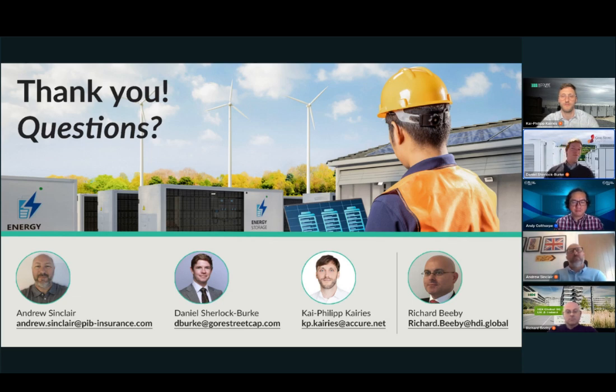I'm not aware of people doing that at the moment. You tend to go over at maintenance visits and do those imaging checks. But honestly, that's unlikely to catch the thermal runaway in time if it was going to happen. It's a useful tool for analysis of the performance of battery racks, and you should use it, but it's not a replacement for this software. It's not going to be as dynamic, and it's not going to warn you as early on, unless you're very lucky and image at the right time.